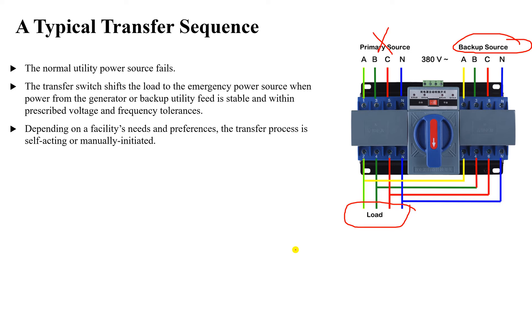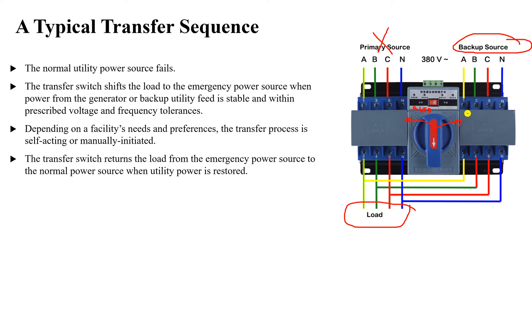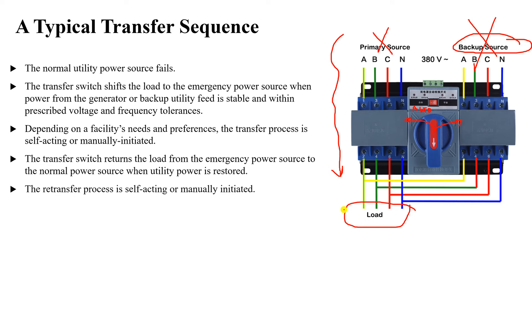Depending on facility needs and preferences, the transfer process can be self-acting or manually initiated. You can see here a switch for auto or manual mode — you can switch between these two modes. When the utility power is restored, the transfer switch returns from the emergency source back to the normal source, turning off the backup and resuming power from the primary source. This re-transfer process can also be self-acting or manually initiated.